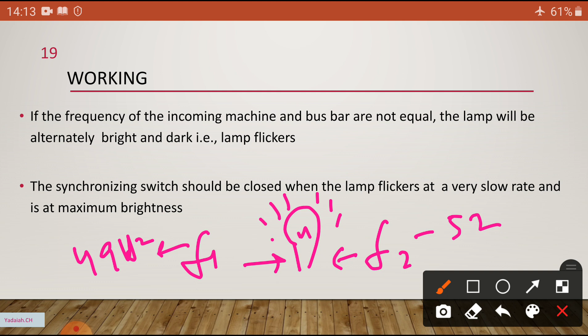The synchronizing switch should be closed when the lamp flickers at a very slow rate. Slowly the bulb glows, slowly it darkens. At that condition we close our synchronizing switch - that is the correct moment (muhurtam) - at maximum brightness, because the total voltage across the bulb is maximum when V1 plus V2 are in phase.